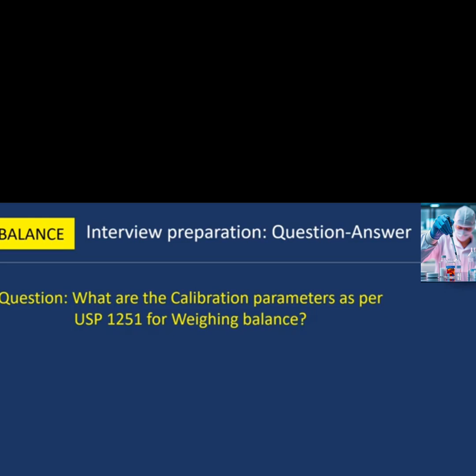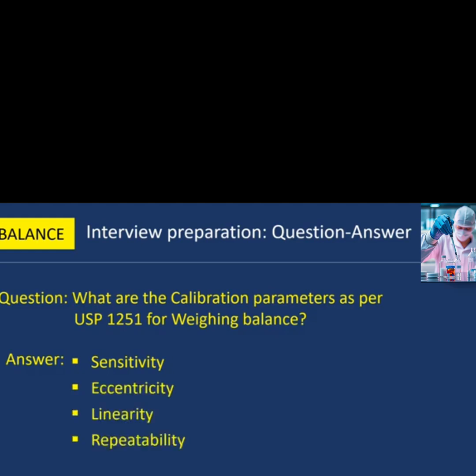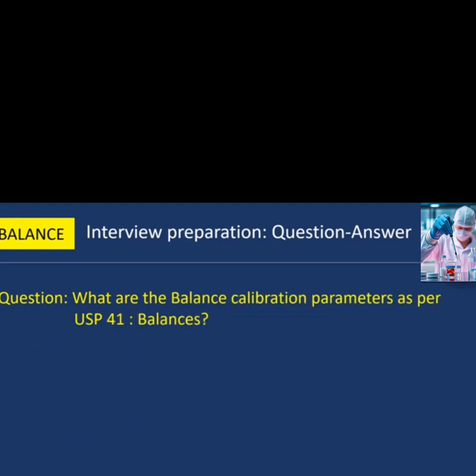Next question: what are the calibration parameters as per USP 1251 for weighing balance? The calibration parameters as per USP 1251 are: first, sensitivity; second, eccentricity; third, linearity; fourth, repeatability.